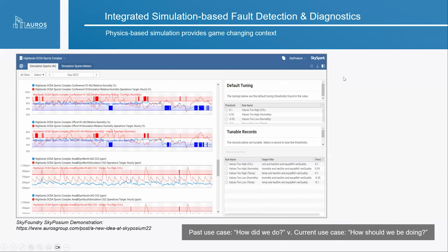But what FDD is, guys, is setting up rules. It's looking at the meter and sensor data for equipment, and it's asking questions. Am I heating and cooling at the same time? We can see that through the trends of the meters and sensors on these equipment. Is a damper open and it should be closed? Is my AHU off and the system's calling it to turn on?